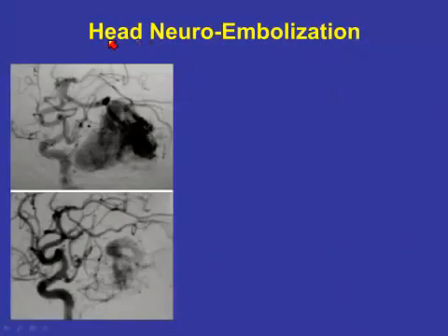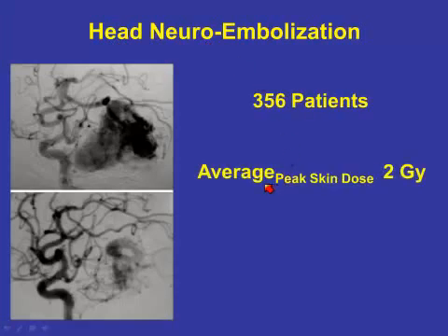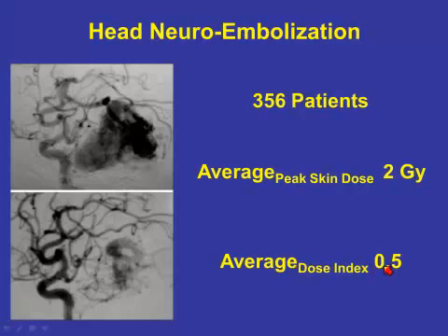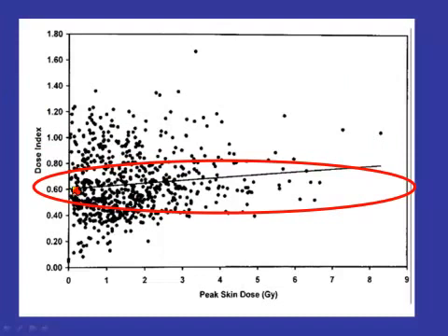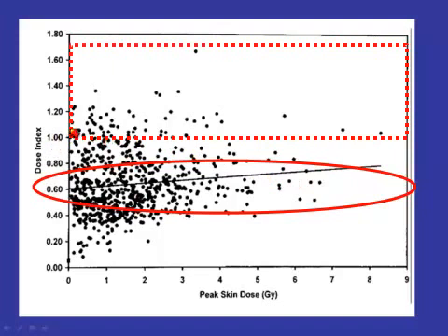And again, if we look at the head neuroembolization data — the 356 patients — the average peak skin dose turned out to be a couple of gray, and the average dose index was about 0.5. So that's good news. In these particular cases, we were overestimating the true peak skin dose. Here's all the data from their study, and what you find is that on average the numbers are like 0.5, 0.6, 0.7, as depicted here. That is the good news. Unfortunately, occasionally we get dose index values higher than one. I'm fairly confident that the dose index for most of your patients is going to be less than one. But in maybe five or ten percent, they will actually be greater than one — and the number you're looking at on your monitor as you do the procedure will actually be underestimating the true peak skin dose.